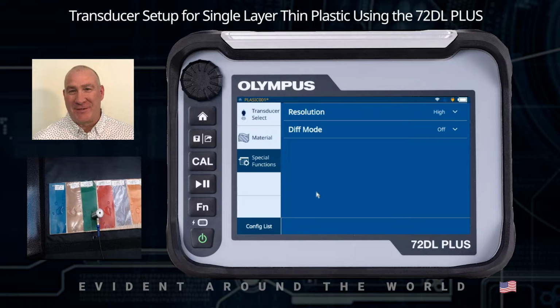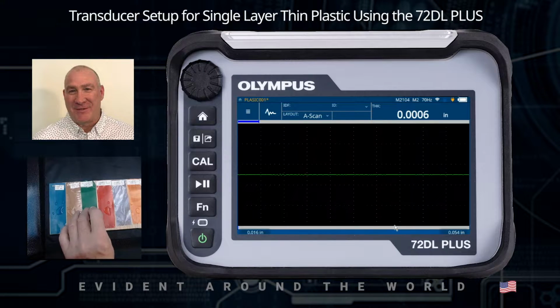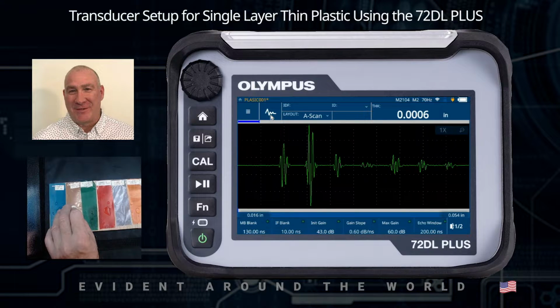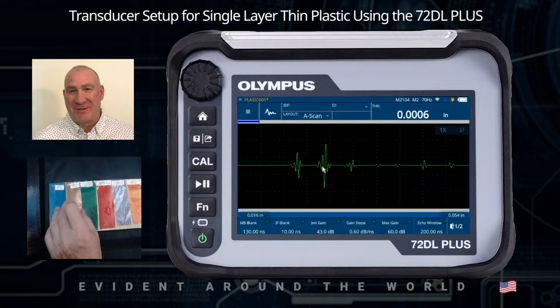And now I can press the home key, which is on the left-hand side of the display, just under the adjustment knob. All right, so if I couple to my sample, I can see I'm starting to see some echoes on screen here. I'm not making detection yet, but that's all right. We'll take care of that in a second. So the first thing I want to do is touch the wave adjust key. At this point, I want to make sure that I'm making proper detection in the area. So if this is my surface echo off the front of the plastic shim and this is the back wall signal, I want to go ahead and adjust my main bang blank and set that just prior to the occurrence of the surface echo.